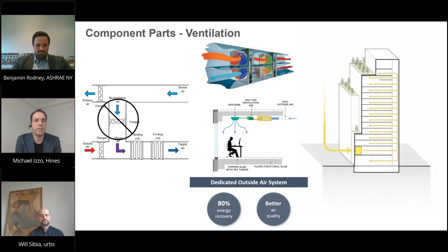On the energy delivery side, we said, what's the most efficient way to activate the building from a thermal standpoint? And this came out of actually some architectural constraints that we benefited from the opportunities. We used radiant slabs for heating and cooling. That allows us to thermally activate the entire building. UC Berkeley did tons and tons of studies, and their studies show that it's 16% greater thermal comfort, and the utilization that we need to activate that structure is only between 60 and 80 degrees. So now our system efficiency is a lot better because we're not making very hot or very cool water. Whereas in a typical building, you would be blowing a lot of hot air and cold air throughout the building.